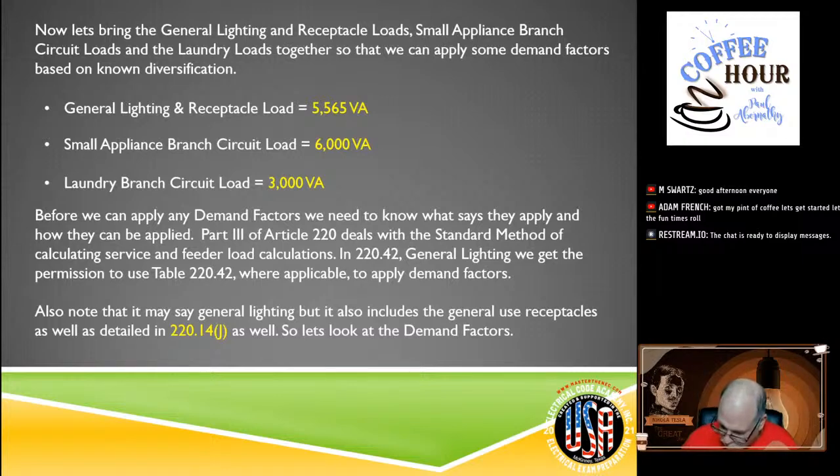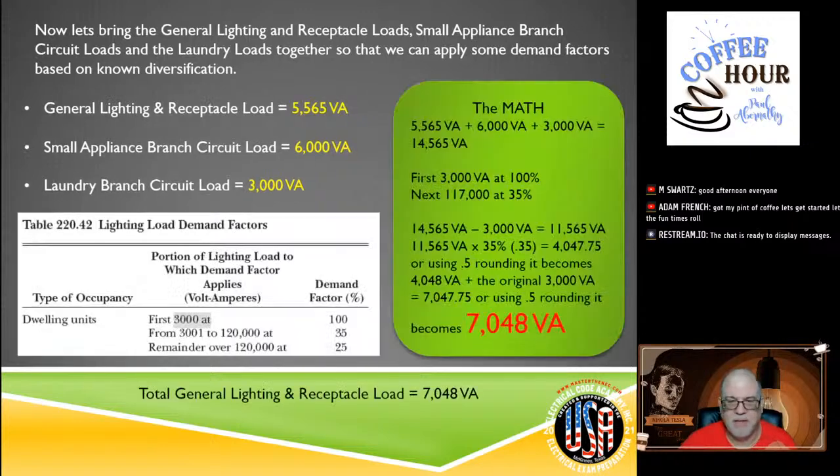And of course, the last one was lighting outlets as specified in 210.70. That's all of the lighting outlets that are required in your dwelling. Those that meet that rule are covered in the 3 VA per square foot. Again, we're talking one family dwelling. All right, so that's where we got that from. I just wanted to make sure everybody was okay with that. Let's keep on going and see how we apply these rules that are in 220.42.